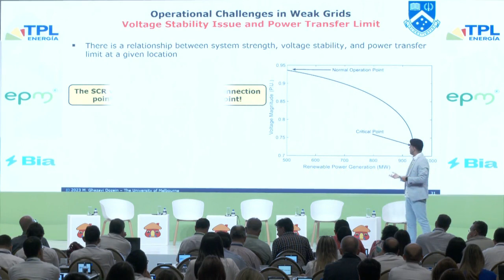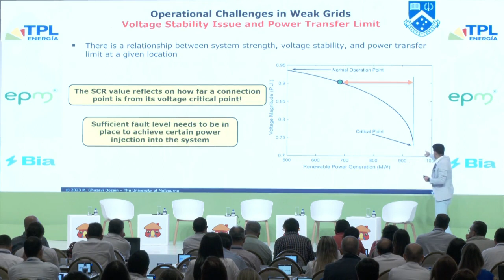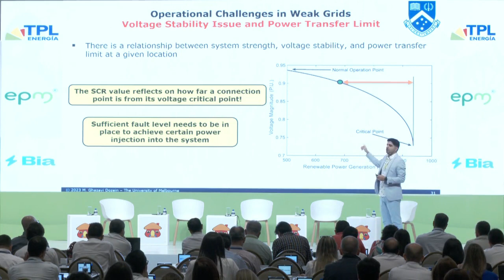When we look at the very classical voltage stability - this is a famous PV nose curve in voltage stability - if you are operating your system here, the short circuit ratio, the fault level, is just relevant to the distance you have from this nose point, the voltage collapse point. So to ensure sufficient voltage stability, you've got to make sure you have sufficient fault level in your system. But what is the potential solution? Because this fault level is coming from synchronous machines.